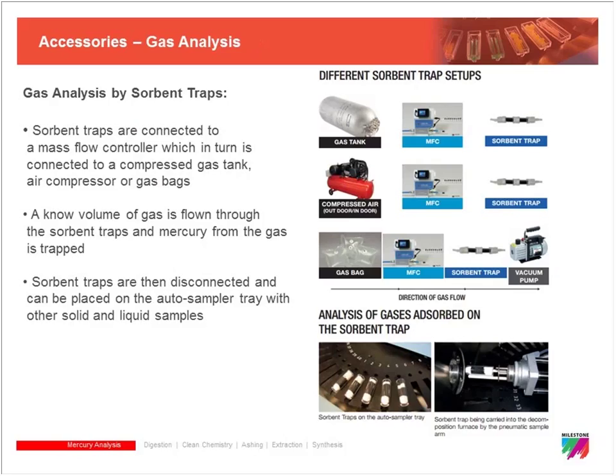We also offer a gas analysis configuration for the system, and how it generally works is you would flow your gaseous sample through a mass flow controller, which will measure the volume of gas. The gas is passed through a sorbent trap, which collects all of your mercury from your gaseous sample. Then these sorbent traps are loaded onto the sampler tray and are analyzed just like any other of your samples. Once the mercury is collected onto the sorbent traps, it's run through the decomposition furnace. All of the mercury is volatilized and analyzed by the system as normal. This is not a very common type of application, but we do have more than a few users regularly analyzing gas, so it does have that functionality as well.